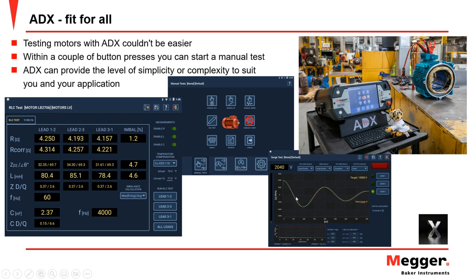If with each pulse from the capacitor we find that there's varying strength of insulation, we'll see this fluctuate, which would indicate that we've got weak turn-to-turn insulation. It's a very quick test, very simple, but gives us the right information to look at the longevity of the motor. Now, this is critical for the predictive element. There are plenty of testers out there, and plenty of competitors that say they can do predictive maintenance on motors. But what they really mean is, yes, we can tell if a motor has failed or if it's good. But with a lot of the tests, such as impedance, resistance, and ground insulation, that doesn't give you the window of what's going to happen in the future.